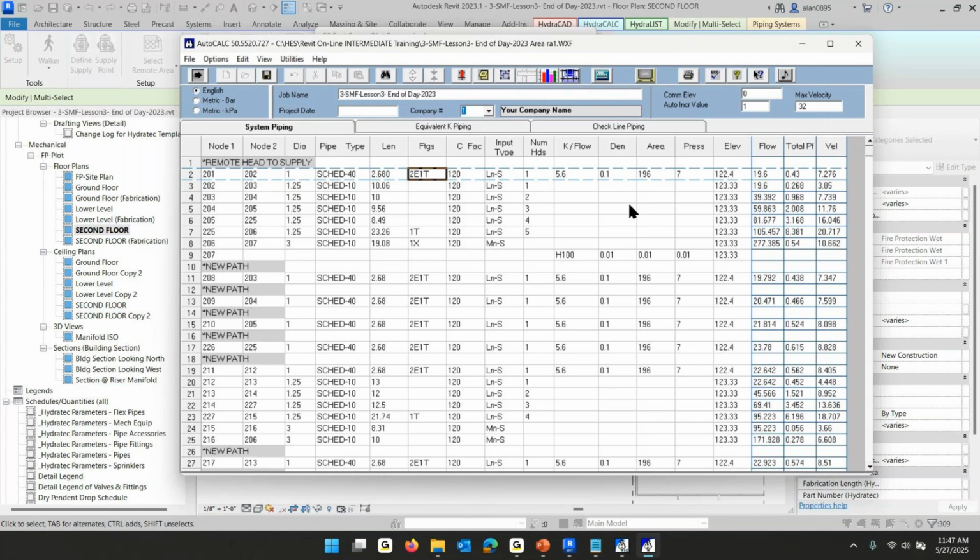Right. Now the supply point's pretty darn close in this system, right? Because we put that right at that elbow. So we went through 1.25 inches, and then we went through 19 feet of 3-inch to get to the supply point. Line 10, row 10 through 17 are the arm-overs feeding that branch line. And then row 18 is the beginning of the next branch line.